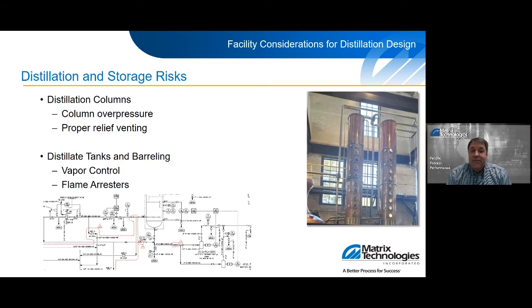But the flame arresters around the distillate tanks, and the emergency venting for dealing with a fire case, are very important around the distillate storage tanks when you've got a 50+% alcohol content within the tanks. So there's several areas involved in unit operations. Those considerations, I still say they're more visible because I'm seeing the tank, seeing the tank full of alcohol.